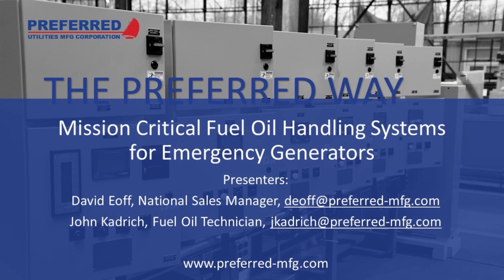Hey, David. So it looks like we do have one other question. It says NFPA 37 has some statements that prohibit valves or traps in overflow piping. In cases where there is not a dedicated overflow line, is it typical that the statement would apply to fuel return piping? On fuel return piping, you're not allowed usually to have solenoids or motorized ball valves or anything that will impede the flow. You can have a check valve, which is always a good idea, because if you have multiple tanks returning fuel, the check valve will keep it from backing up into another tank. But usually solenoids are a bad idea.